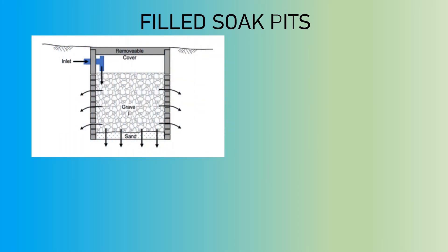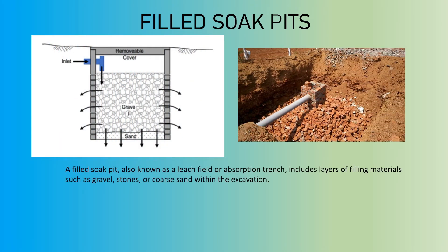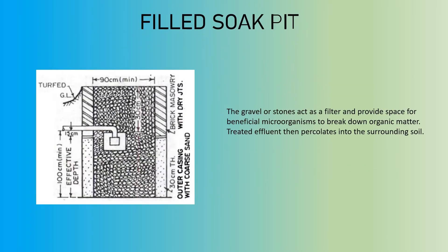A filled soak pit, also known as a leach field or absorption trench, includes layers of filling materials such as gravel, stones, or coarse sand within the excavation. Wastewater flows into the filled soak pit where it encounters the filling material, which provides additional surface area for the wastewater to interact with and facilitates better distribution of the effluent. As the wastewater moves through the layers of filling material, it is treated through physical and biological processes. The gravel or stones act as a filter and provide space for beneficial microorganisms to break down organic matter. Treated effluent then percolates into the surrounding soil.